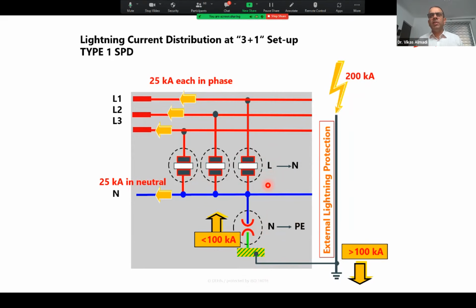Now, as I told you, I will tell you the designing of this. 10 by 350, 8 by 20, you have already understood. And second thing is, let us say the total lightning is 200 kiloampere. 50% of that goes to ground. The balance 50% is for the power line. Because out of this 100 kiloampere which is left over, most of this will go into the power line because of the conductors, very good conductors of the power line. Metal pipelines, IT lines, they will have the current.